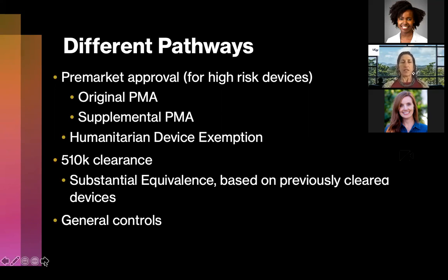There are some other ways I'll spend a little time talking about, such as the humanitarian device exemption. There's also 510K clearance, which, unlike the pre-market approval, doesn't require any clinical data. What you have to show in this pathway is substantial equivalence - that it has to be substantially equivalent to a device already on the market, which is also called a predicate device. Then for low-risk devices, there's general controls, which is essentially filing paperwork.